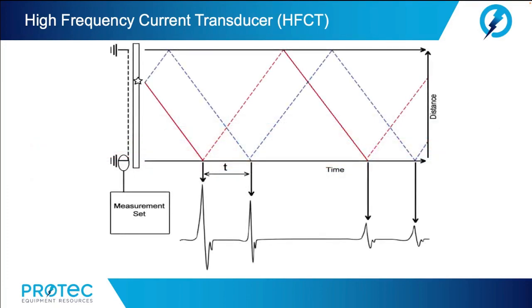In cable PD testing, the localization of PD via the HFCT sensor is achieved by determining the time difference between the arrival of the initial PD pulse and the reflected pulse, which has reflected off the opposite end of the cable where you're testing. The speed of the pulses on the cable is like the speed of light. Exact signal speeds are known for various cable types. Knowing the speed, the cable length, and the time difference of arrival between the initial pulse and the reflected pulse enables the calculation of the distance to the partial discharge. Online cable PD testing instruments many times will have functions to identify these pulses and perform distance calculations.